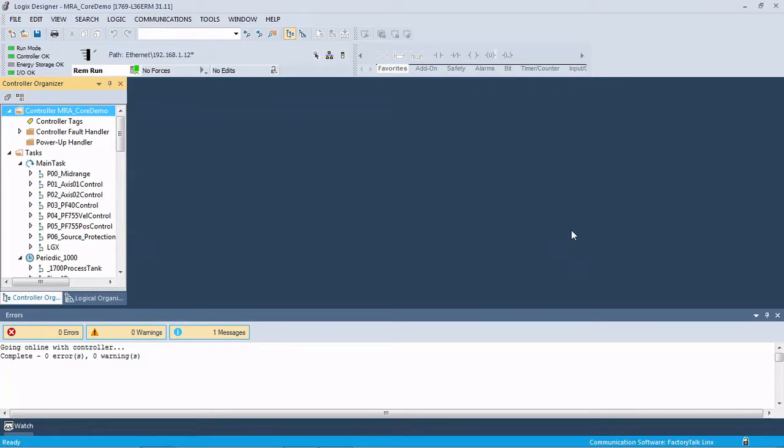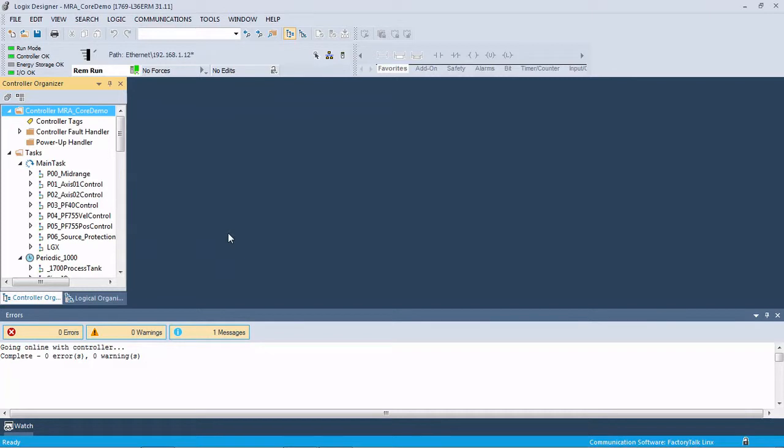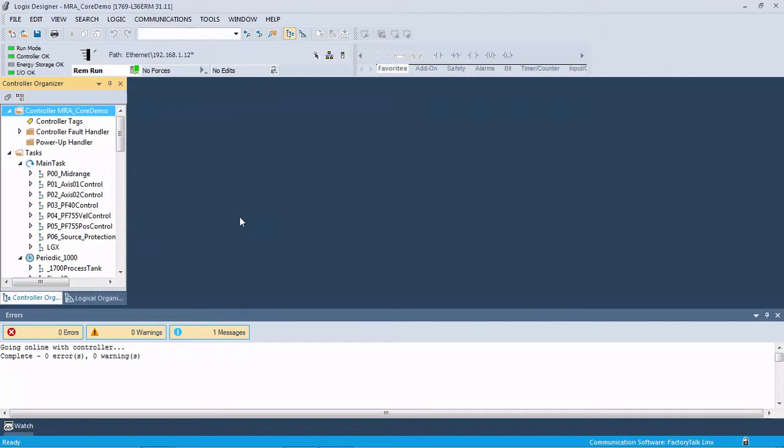First thing is your running system. You cannot do the prep work for this unless you can take the controller out of run mode, so you have to be able to take the system down. A good time to do this would be when startup on the machine is done and up and running. Also to note, after any changes are done, this procedure must also be done, or else when you restart the PLC and power it back up, the old program is going to overwrite any of those changes that were made. So you want to make sure anytime there's changes made that this procedure is done.